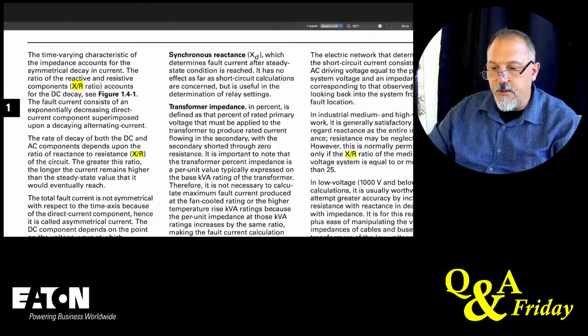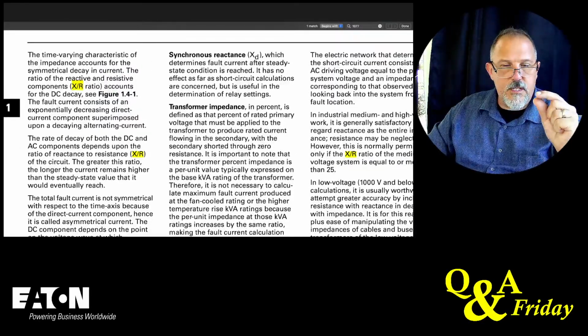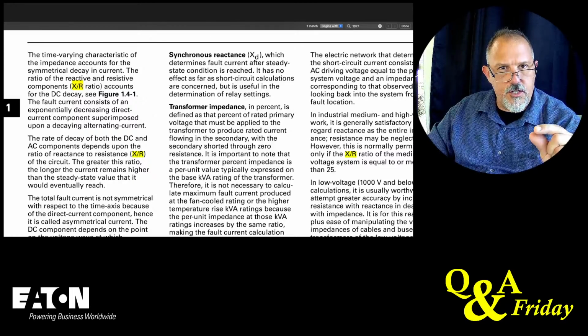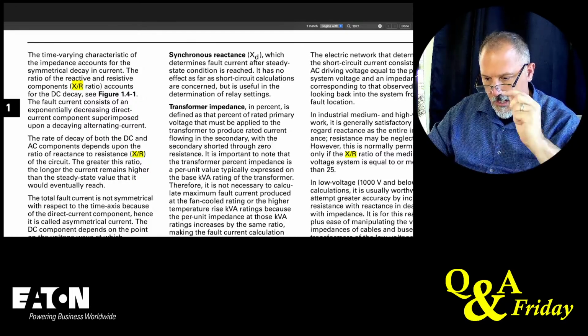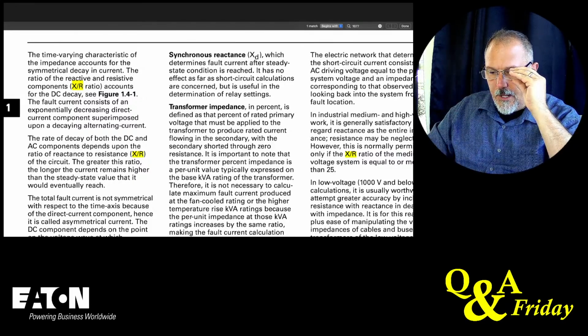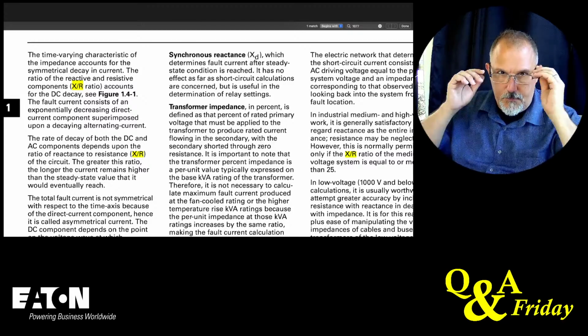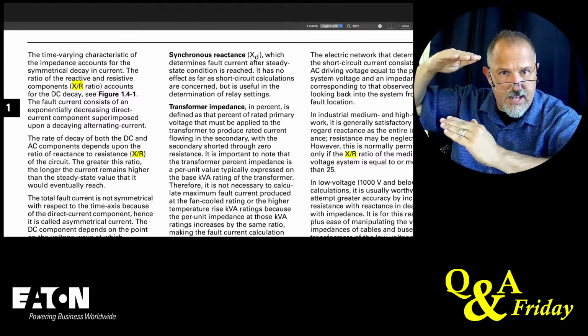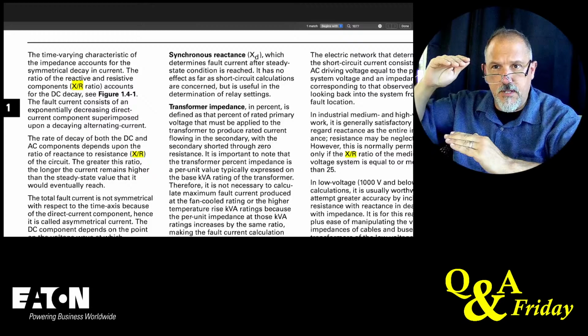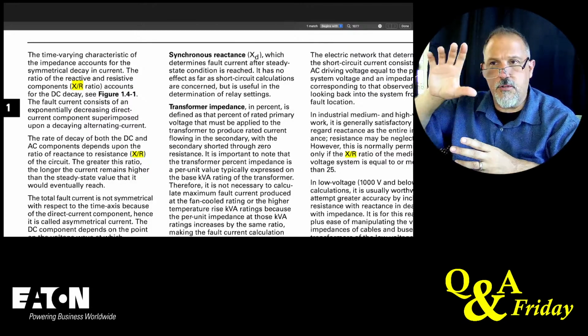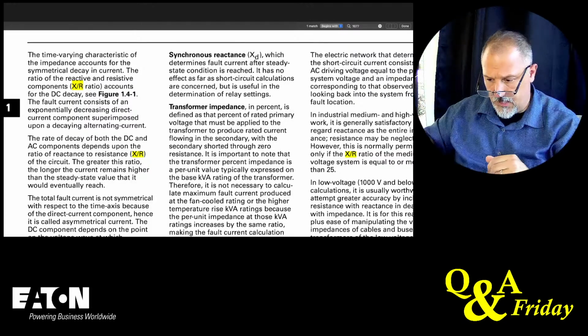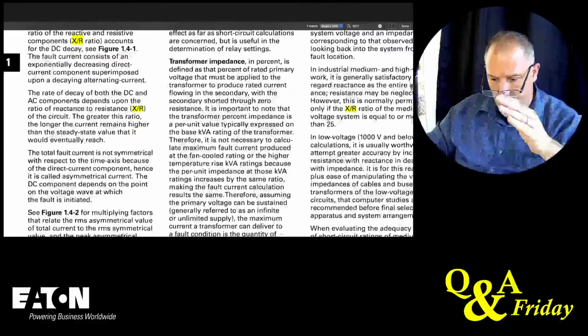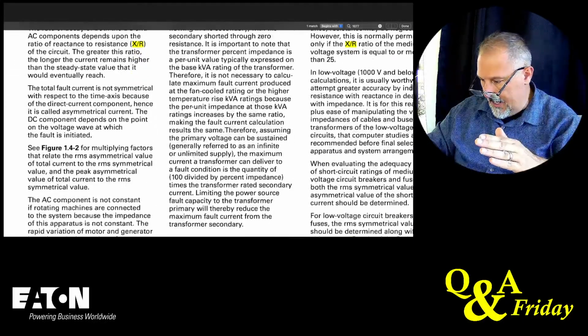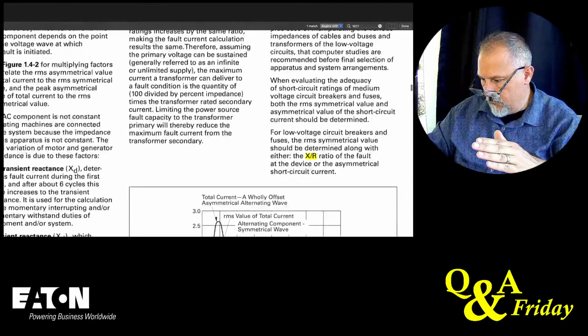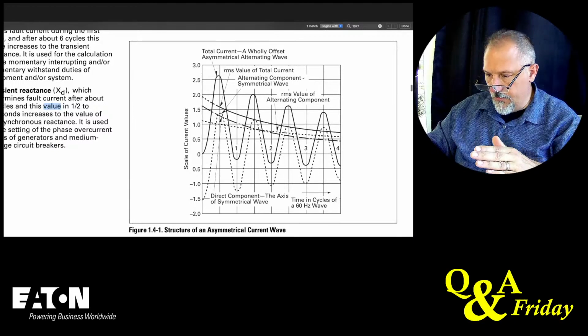The time varying characteristic of the impedance. This is the X. X is your reactance. R is your resistance. This determines the peak of your first half cycle. The X to R ratio determines how long it will take to decay down to a symmetrical current, and that rate of decay. And this is what we're talking about.